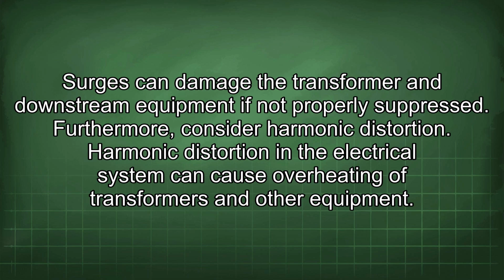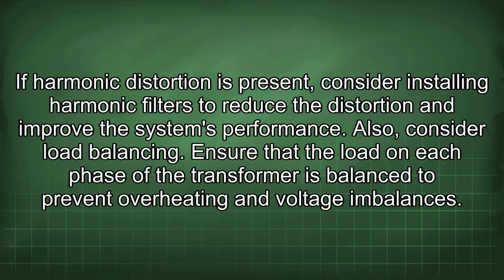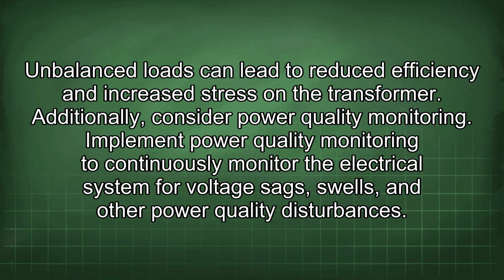Furthermore, consider harmonic distortion. Harmonic distortion in the electrical system can cause overheating of transformers and other equipment. If harmonic distortion is present, consider installing harmonic filters to reduce the distortion and improve the system's performance. Also, consider load balancing. Ensure that the load on each phase of the transformer is balanced to prevent overheating and voltage imbalances. Unbalanced loads can lead to reduced efficiency and increased stress in the transformer.